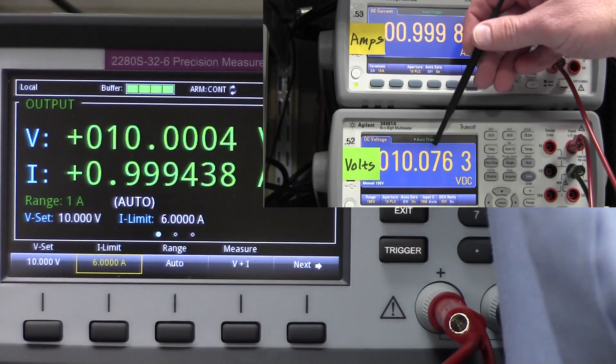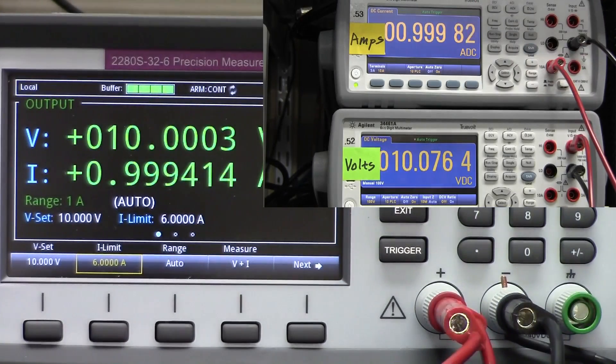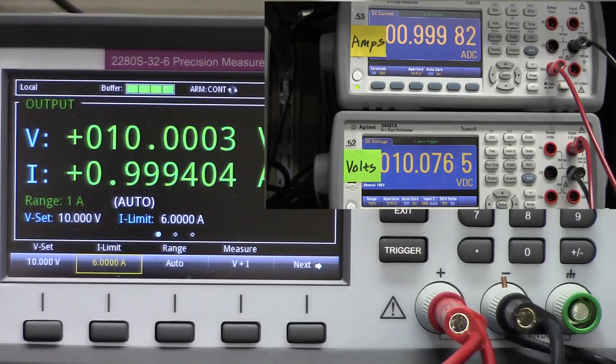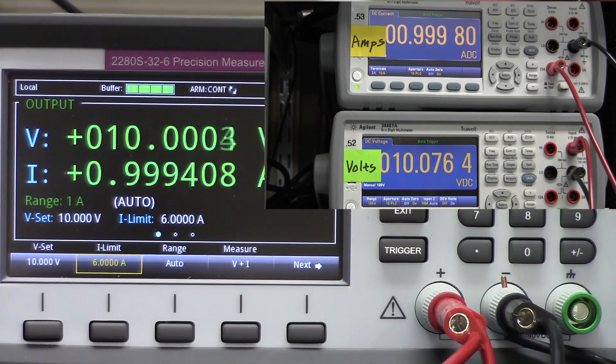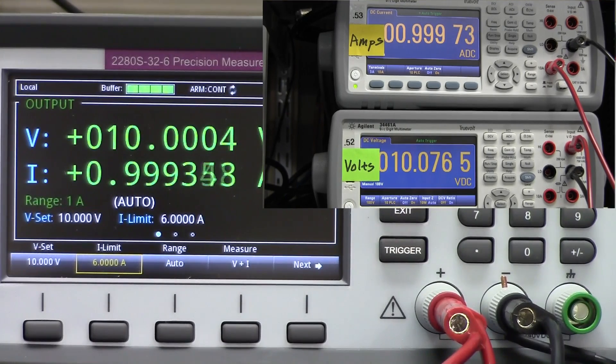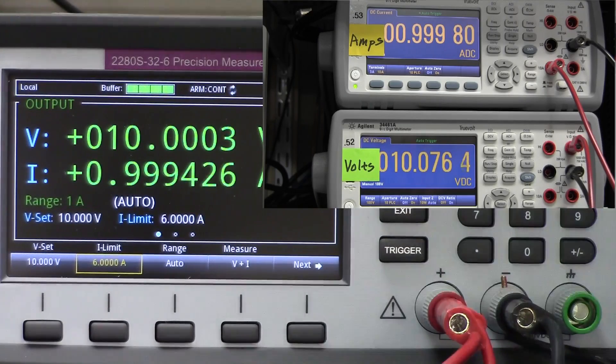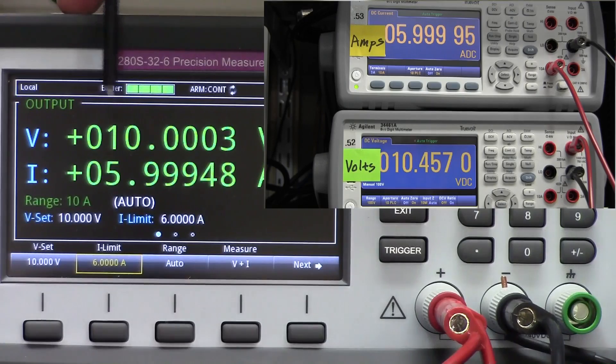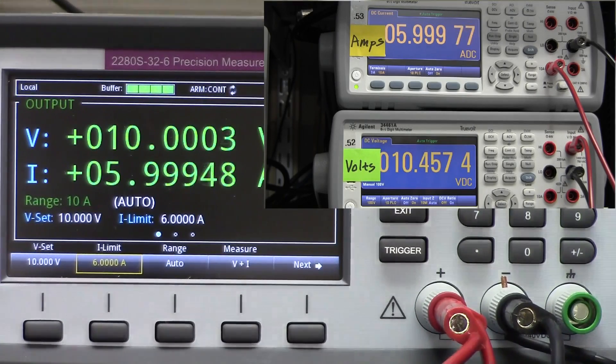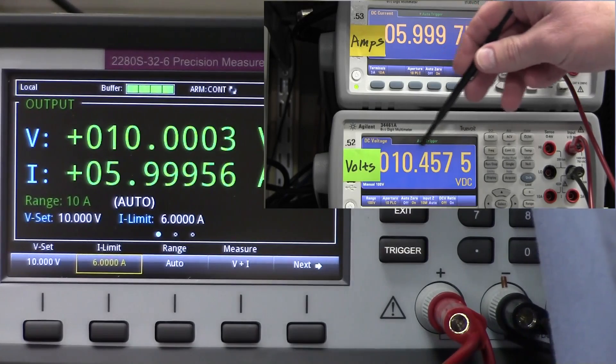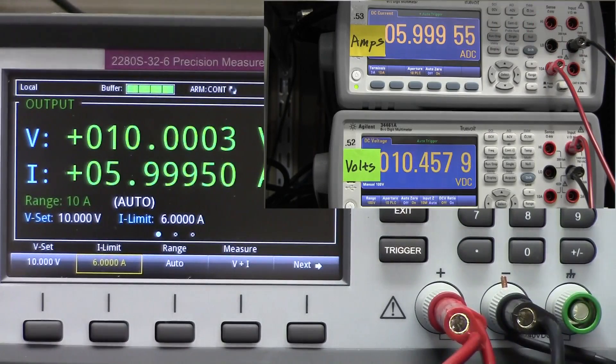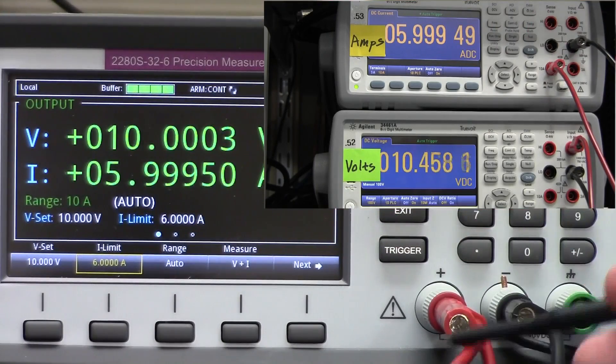If we turn the load back on, but instead let's turn it all the way up to 6 amps, 10.0003, 10.0004, but up here we're reading 10.457. So we're reading an increase of nearly half a volt. So in order to make up for the losses in these wires here, the power supply is pumping out an extra half volt.